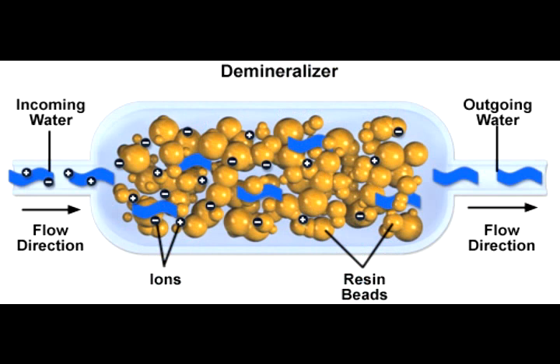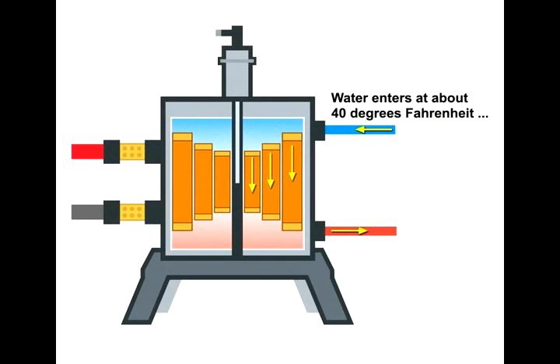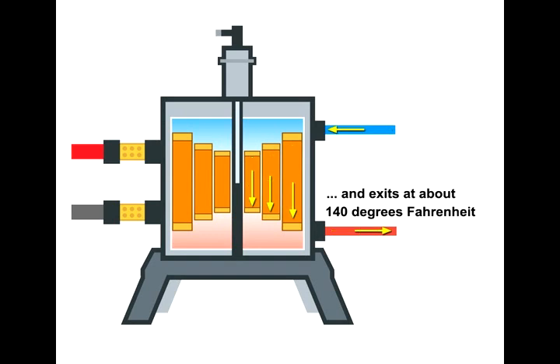Now the water goes into the magnet about 42 degrees Fahrenheit and can come out about 140 degrees Fahrenheit. So we have about a 98 degree temperature rise over a distance maybe 2 feet tall.